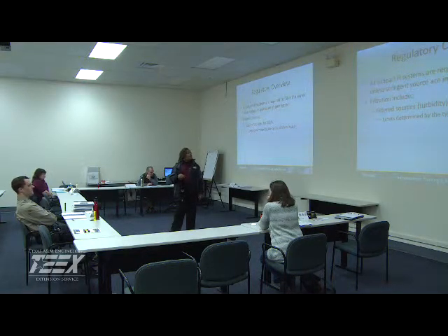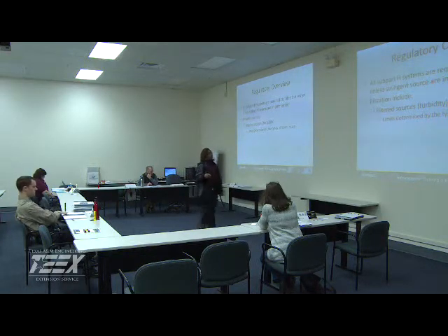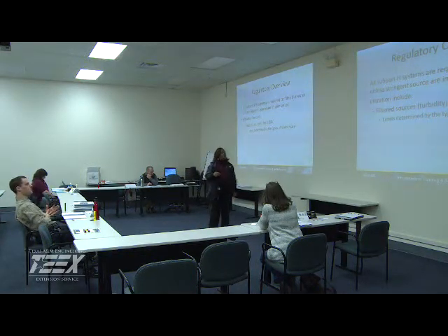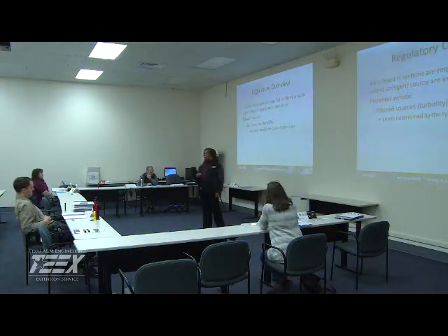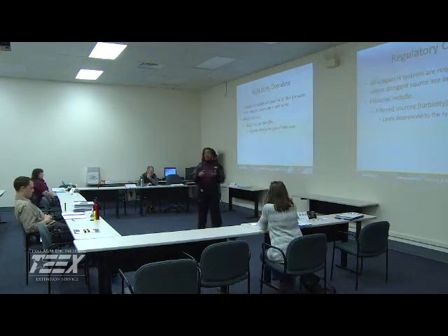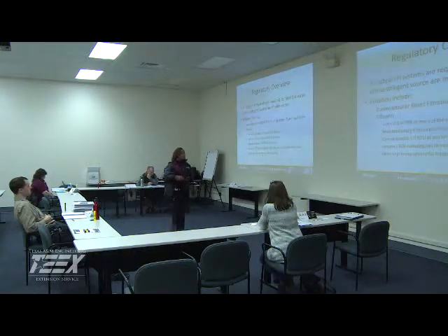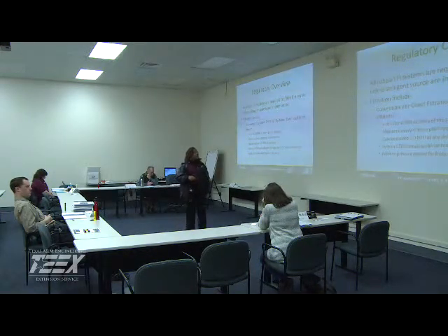All right, for the filtered sources, and this is where you come in, the limits are determined by the type of filters in use. What this is saying is that you want to make sure that your filters are able to meet the requirements. Whether you're doing combined or looking at individual filters, 9 times out of 10, that's going to be equal to or less than 0.3 NTUs in at least 95% of your monthly samples.